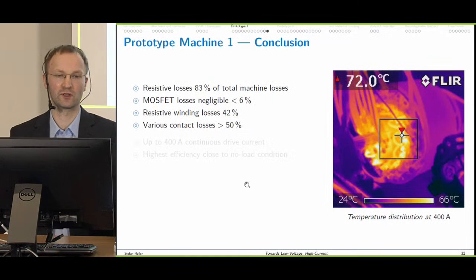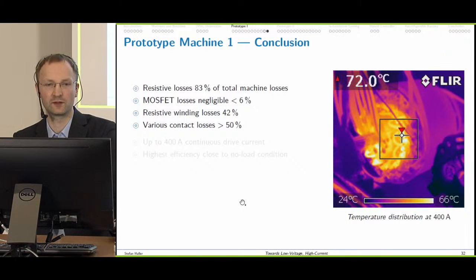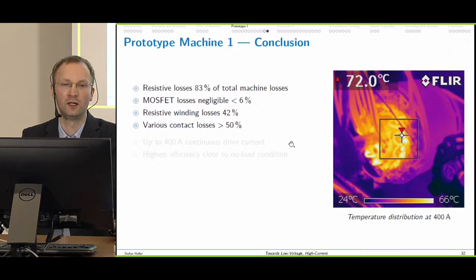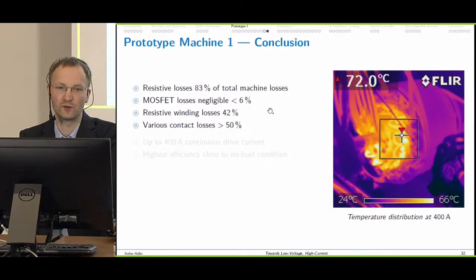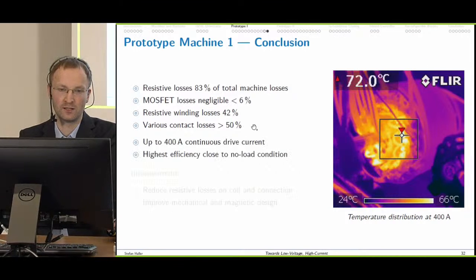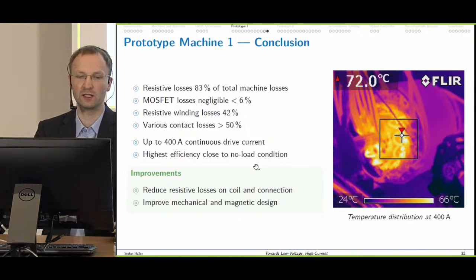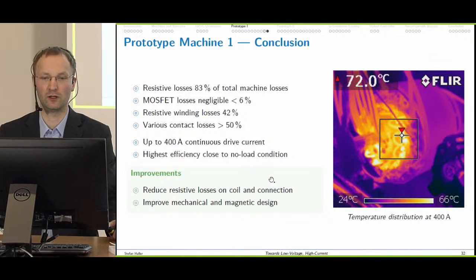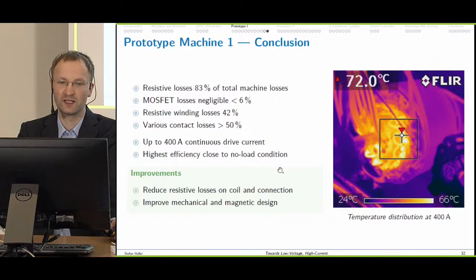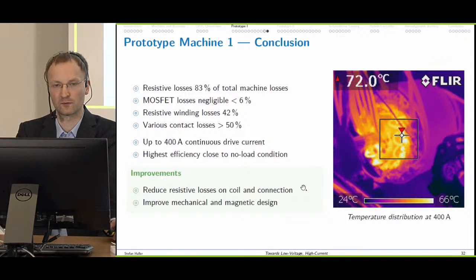To conclude on the first machine, resistive losses are 83% of the total machine losses, so fairly too much. MOSFET losses are negligible, resistive winding losses are 42%, and various contact losses more than 50%. The highest efficiency was close to the no-load condition. As improvements for the next prototype, we drastically need to reduce the resistive losses and coil connections, and we need to improve the mechanical and magnetic design. As we heard in the video, the machine was vibrating quite a lot, and we had some hassle assembling it.